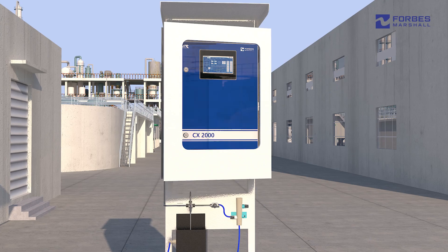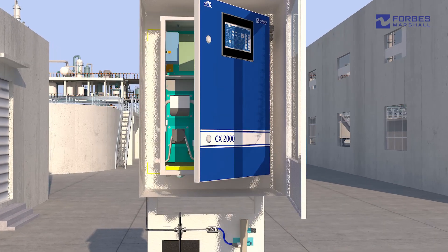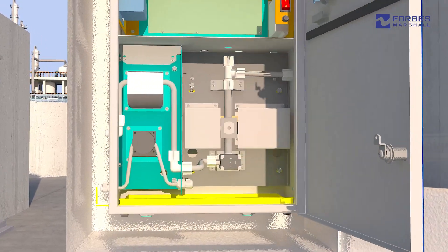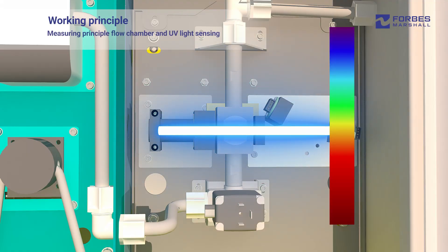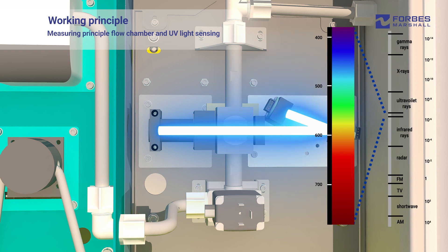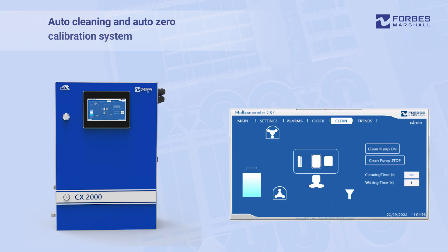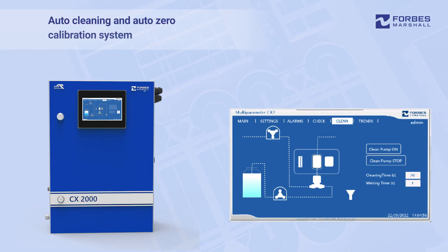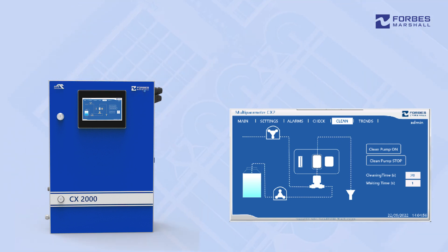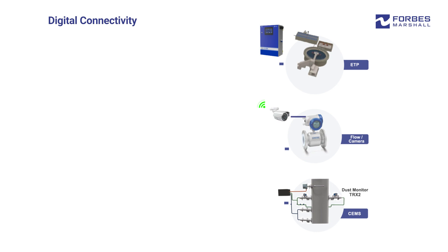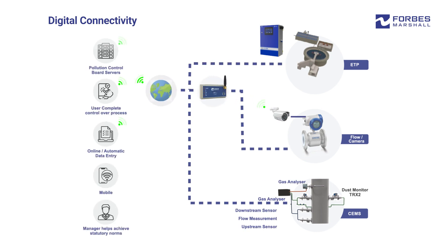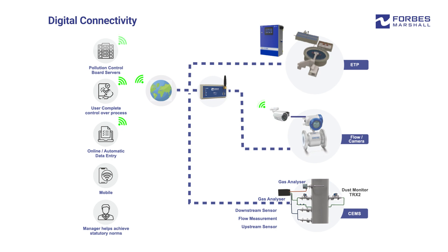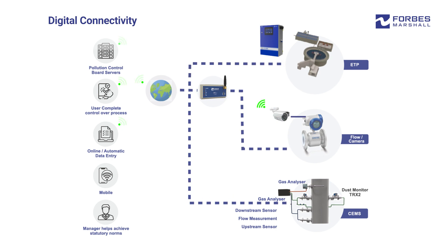The measuring principle of the CX2000 is based on UV visible light absorption dual beam spectroscopy. The auto-cleaning feature ensures flow cell cleaning and zero drift correction. Through remote real-time monitoring, diagnostics are provided to help users plan corrective actions where required and ensure high uptime of the analyzer.